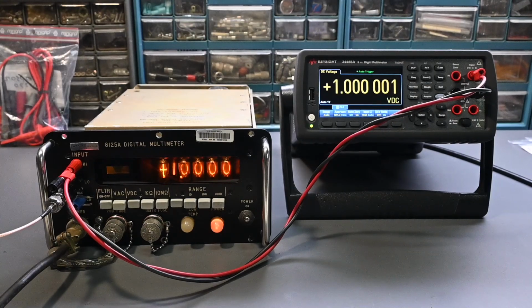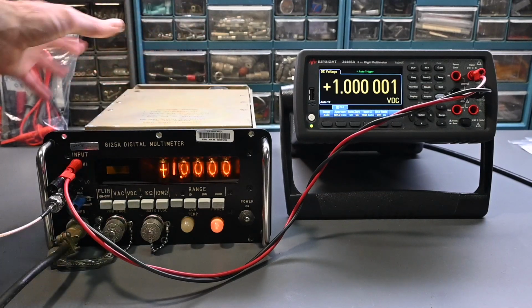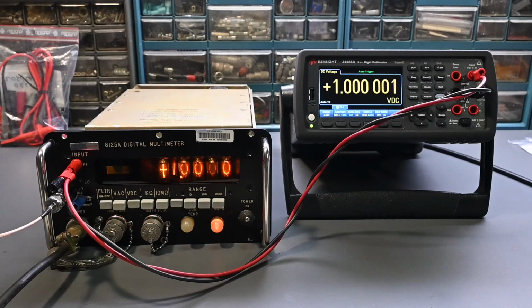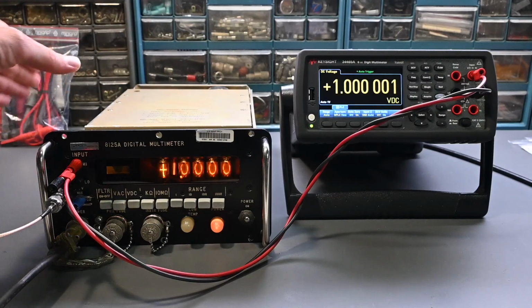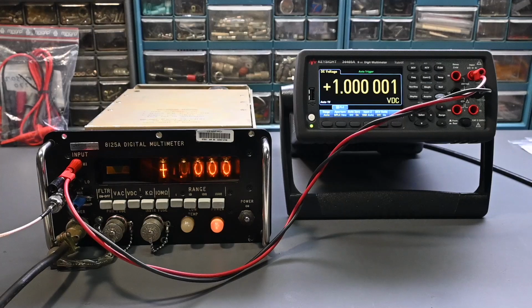Now, obviously, when you're doing this calibration, you want to have the metal shields installed first and then do the calibration, because if you calibrate the instrument and then put the shields in place, it could throw the calibration off. Now, this top shield right here and the shield on the bottom are electrically floating or isolated from the frame or chassis of the instrument, so it's also important that those not be shorting out against the side rails or something like that. And there are some nylon standoffs that hold everything in place and keep it isolated and insulated.